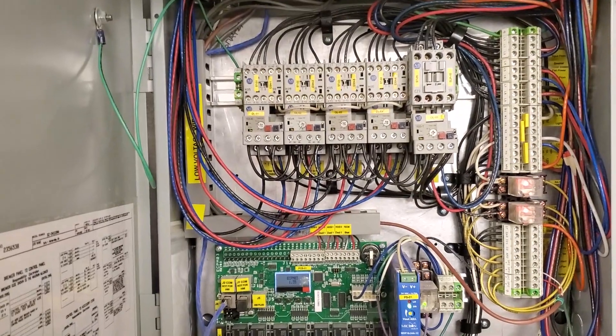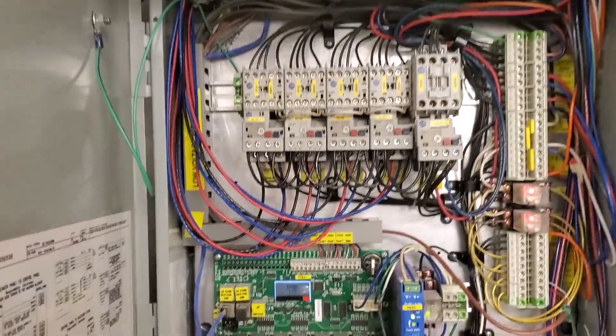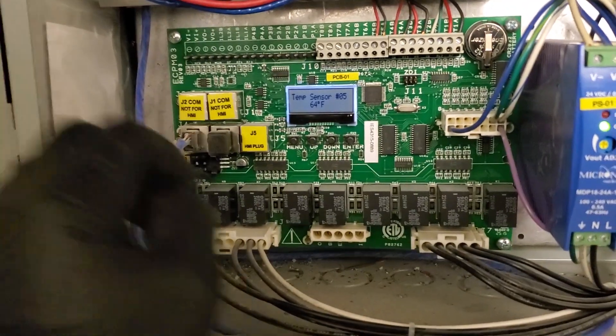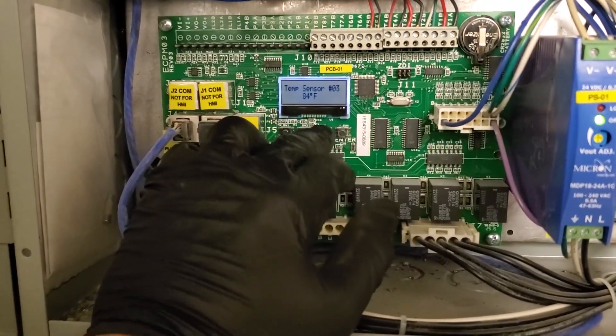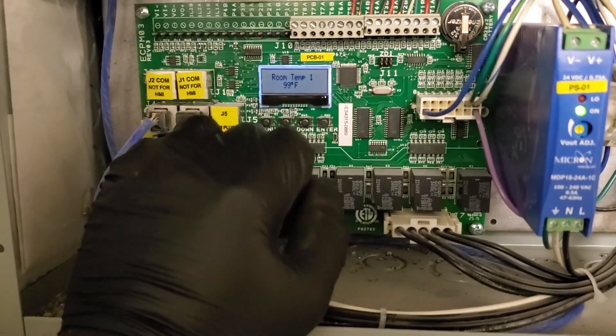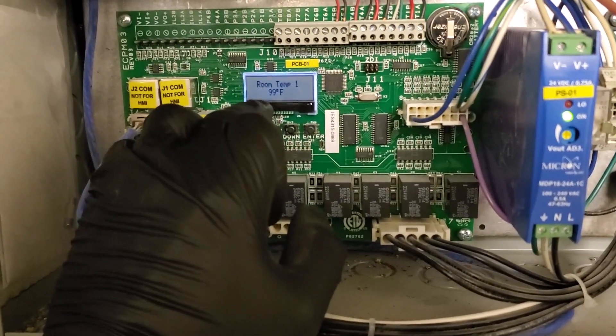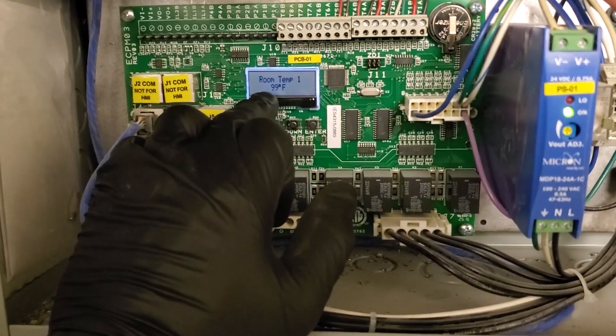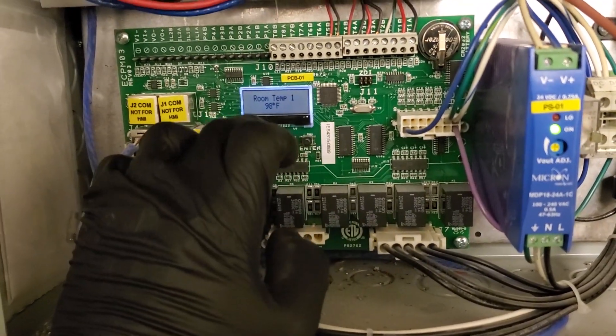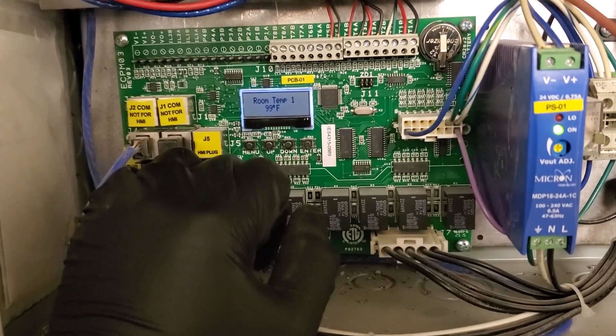I'm going to call Captive-Aire tech support real quick and just run my theory by them. I believe my theory is confirmed. After talking to Captive-Aire tech support, I'm very worried about room temperature number one being 99 degrees. It is not 99 degrees in the building — this should be an actual room temperature. I'm worried that it says 99 degrees because nowhere in this kitchen is it 99 degrees right now, and that could lead to the problem of the on-off thing.